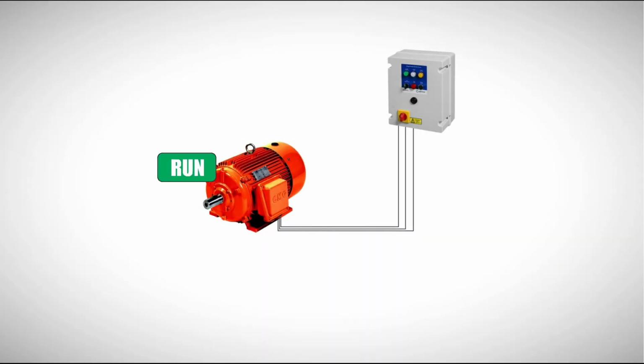If you set the delay to 2 seconds, the relay won't react immediately when voltage drops. It will wait. So if the voltage dips briefly, say for half a second when a motor starts, the relay simply ignores it because the system recovers quickly. But if the voltage stays low for more than 2 seconds, that's when the relay steps in and trips. In short, it filters out short disturbances and only reacts to real problems.